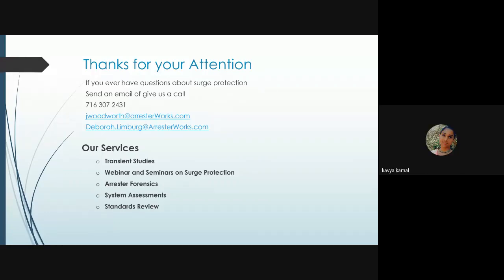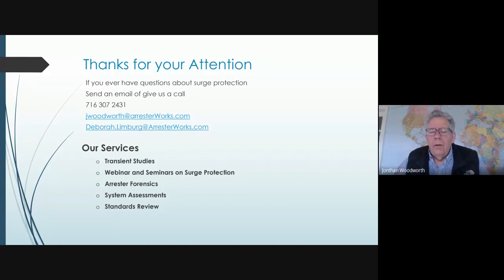Next, what is the difference between surge arrestor and lightning arrestor? Nothing really. Their terms are used interchangeably quite a bit. The arresters that are mounted in a substation deal with switching surges and lightning surges, so they really handle all kinds of surges. The arresters applied out on the distribution system really only deal with lightning surges. They don't really deal with switching surges. So it's more like a lightning arrestor only, where the arrestor in a substation would be for lightning surges and switching surges. It's really being picky to say they're different, but they're just the slightest difference. But many people use the terms completely interchangeably.